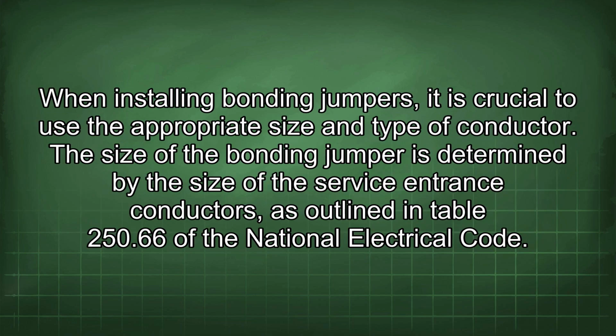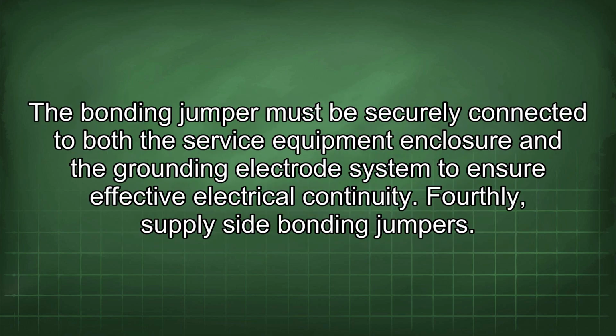When installing bonding jumpers, it is crucial to use the appropriate size and type of conductor. The size of the bonding jumper is determined by the size of the service entrance conductors, as outlined in Table 250.66 of the National Electrical Code. The bonding jumper must be securely connected to both the service equipment enclosure and the grounding electrode system to ensure effective electrical continuity.